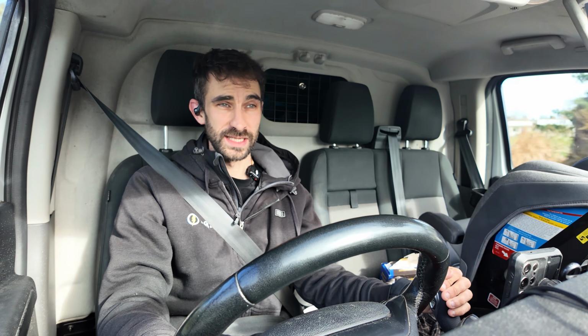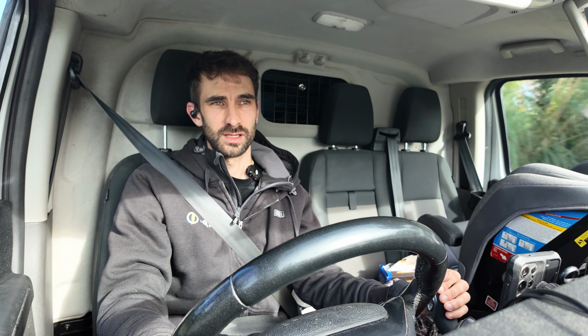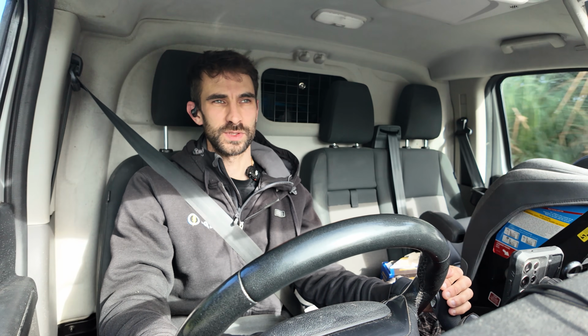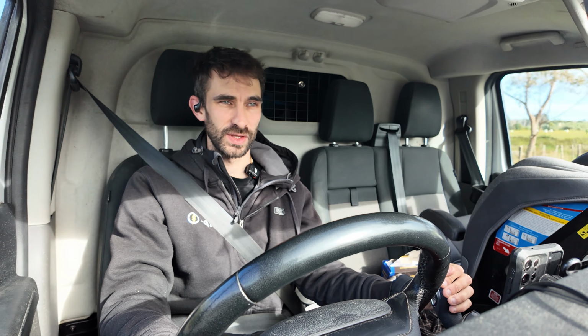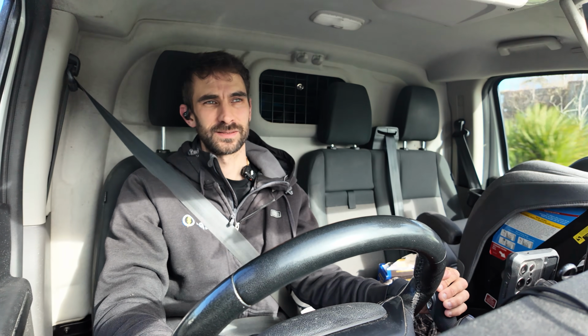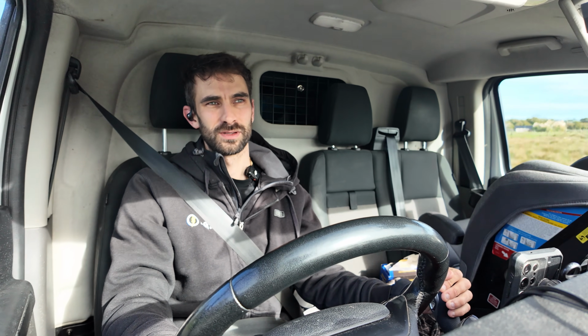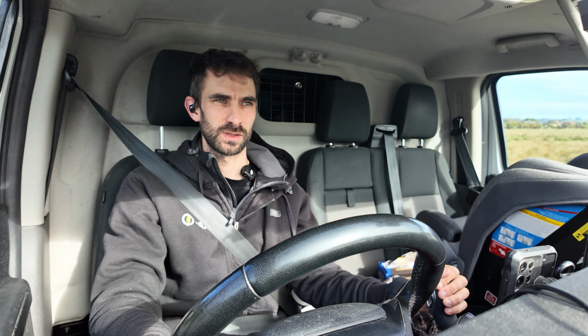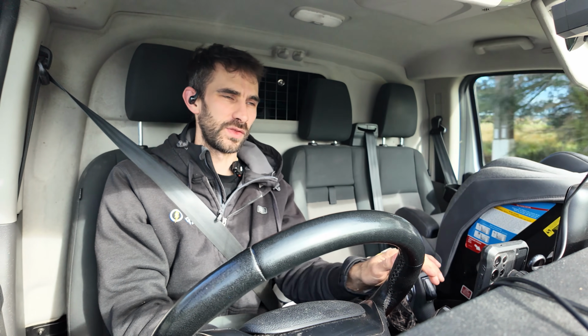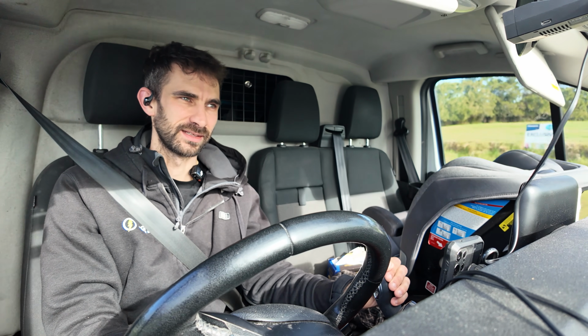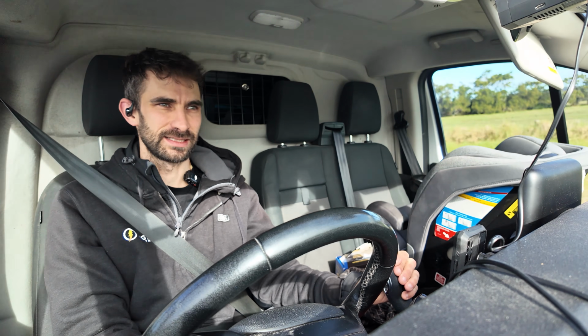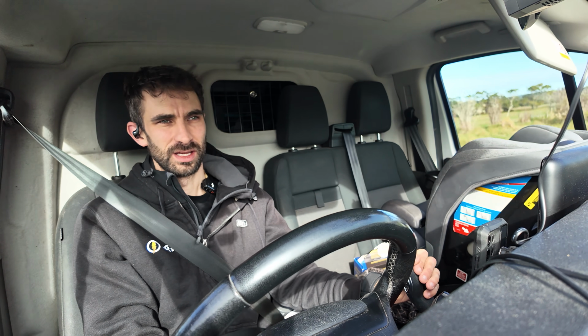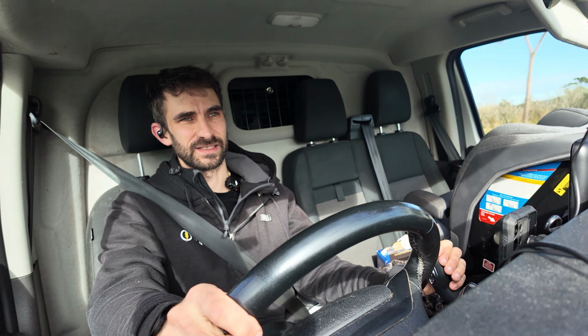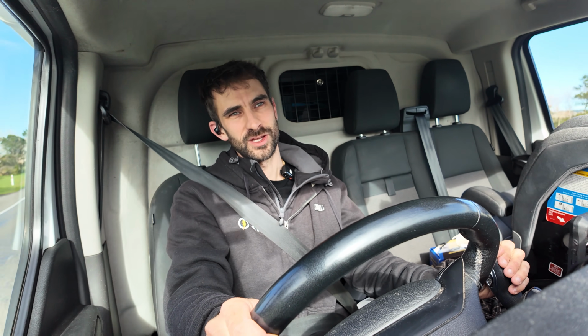But we test the continuity. You've got to get half an ohm continuity between the main earth electrode and the main earth bar back in the main switchboard. But for the earth rod, there's nothing. There's no test to make sure the earth rod is achieving a good conductive path with the earth mass, which to me says it's not really doing anything important.